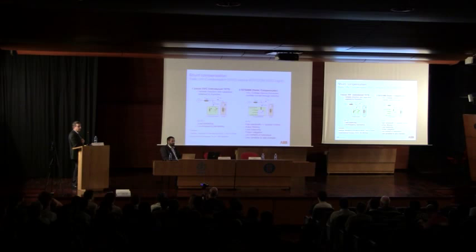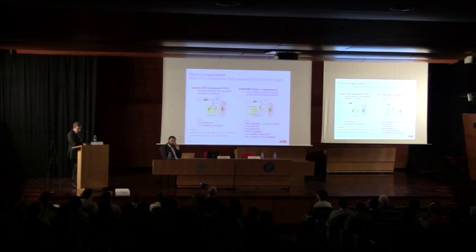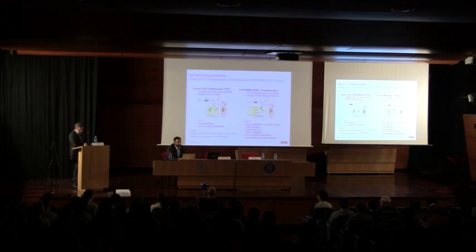And when we are using voltage source converters with transistors, we can switch quite fast, so we have a higher bandwidth. With this bandwidth, we can do more things like active filtering. If we have a load with a lot of reactive power changes, and we get flicker problems, we can mitigate this flicker by having a high bandwidth on the reactive power we are injecting to the grid. And we have less low-frequency harmonics, so we need fewer passive filters, which is really good.